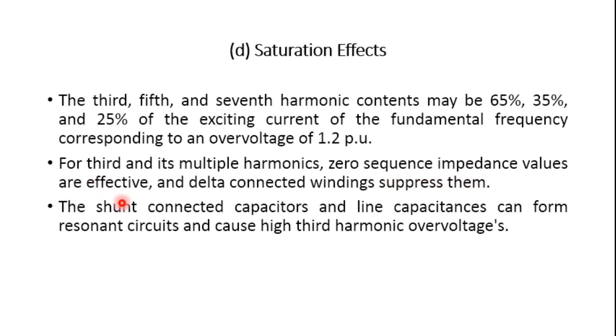If zero sequence impedance values are significant and the winding is connected star to delta, the third harmonic currents circulate within the transformer legs. The shunt-connected capacitors and line capacitances form a resonance circuit, causing high third harmonic overvoltages. When such overvoltages are added, the rise in voltage in the lines may be significant for higher harmonics, and a series resonance between the transformer inductance and the line capacitances can produce even higher voltages.